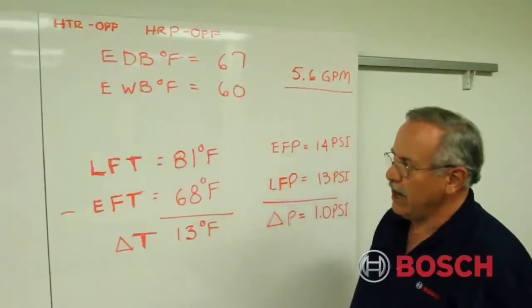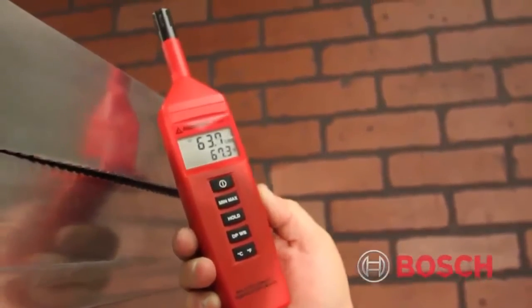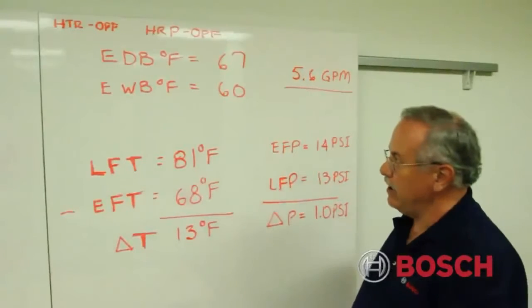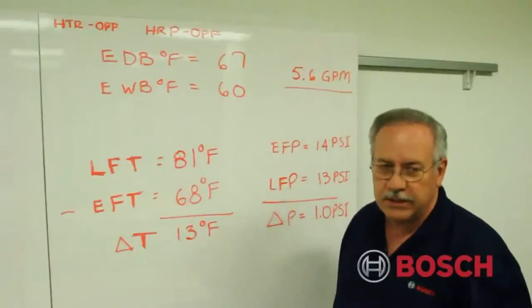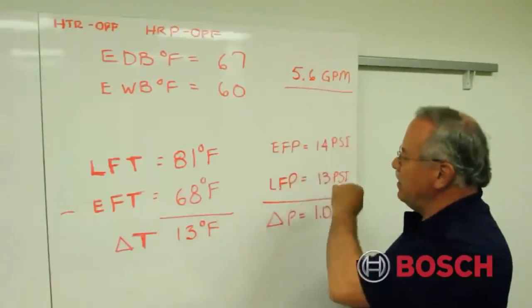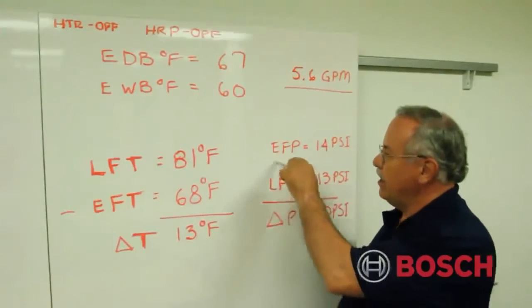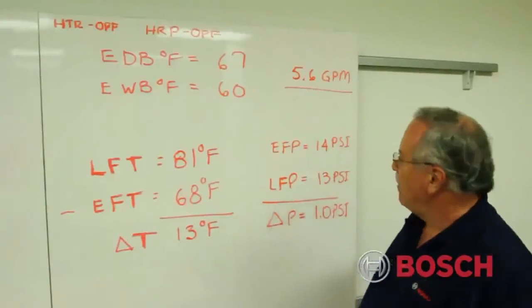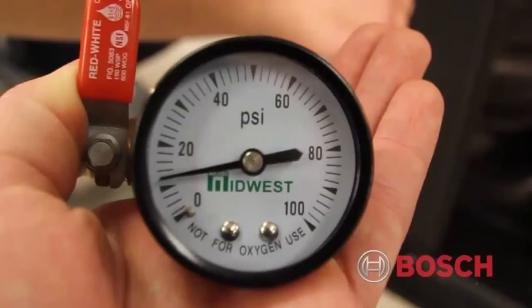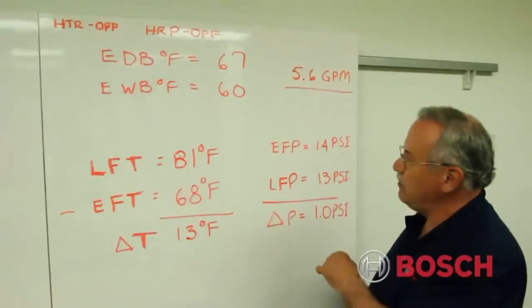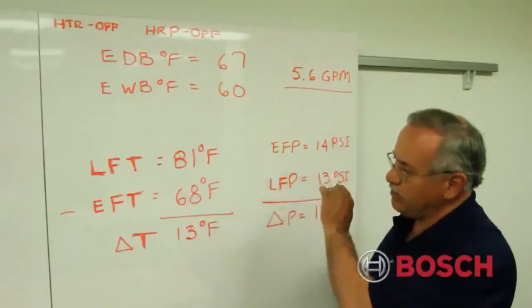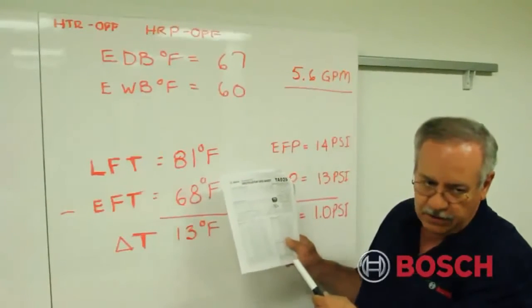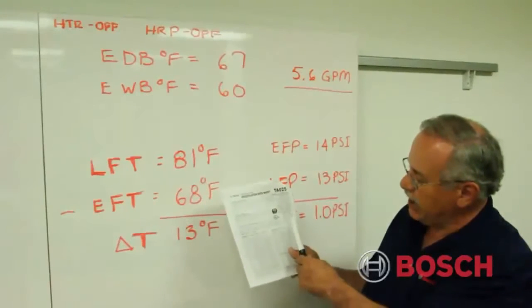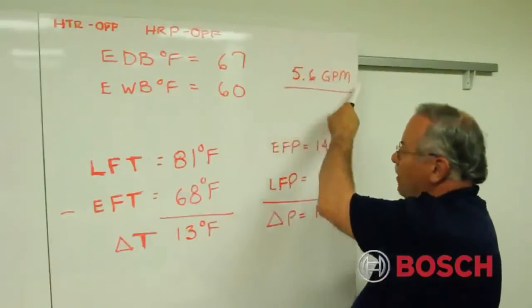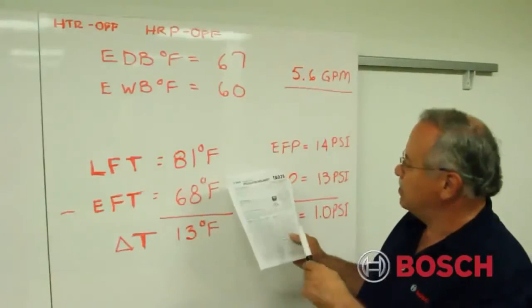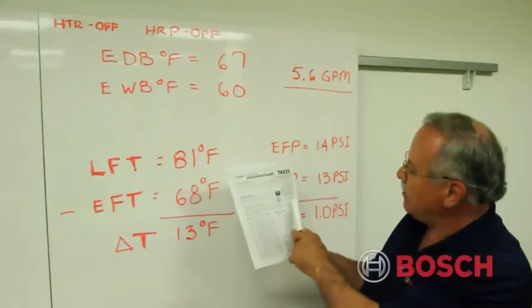Additionally, Mark had to gather the data with a digital psychrometer at the return. He had to determine the entering dry bulb temperature, which he found at 67, and the entering wet bulb temperature at approximately 60 degrees. Then he determined from the coaxial the entering fluid pressure and the leaving fluid pressure of 14 psi and 13 psi, so roughly he found a pressure drop, or delta P, of about 1 psig. So we take this information and we go to the current TA025 full load data. On the middle of the right side of the page, you're going to find in the spec data fluid pressure drop.